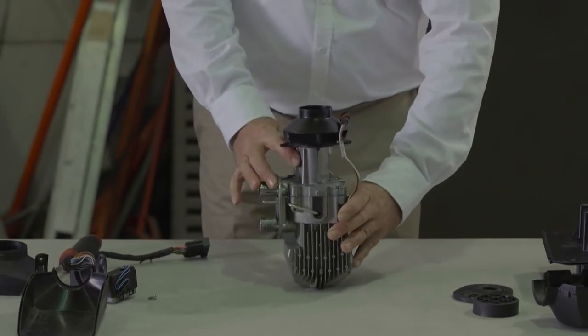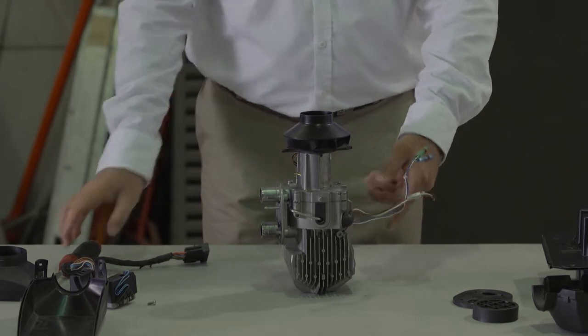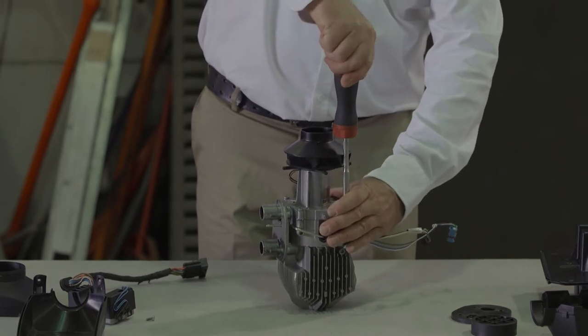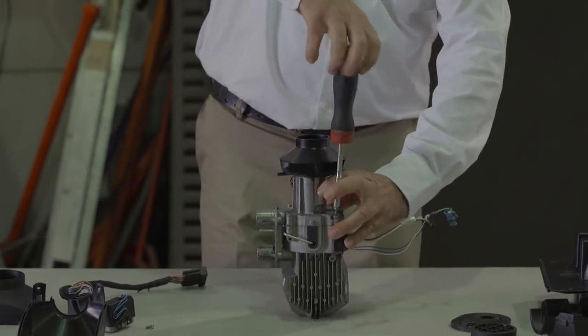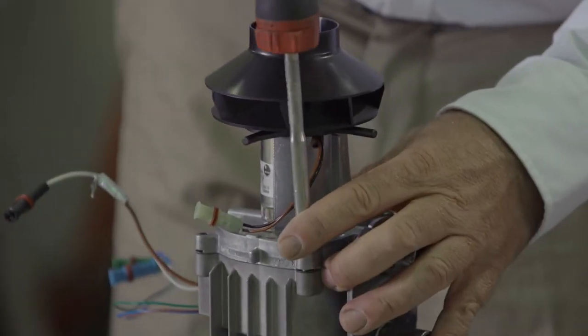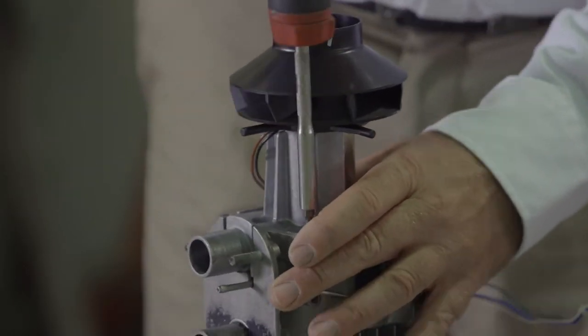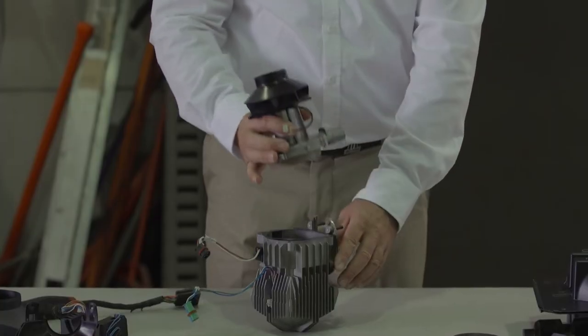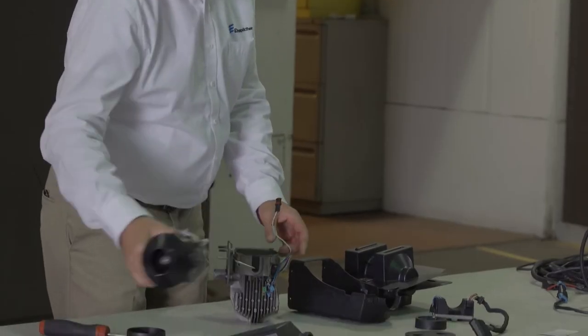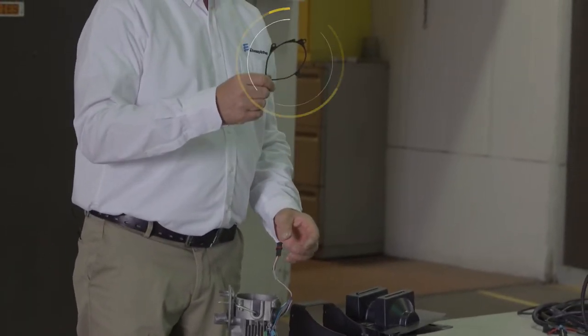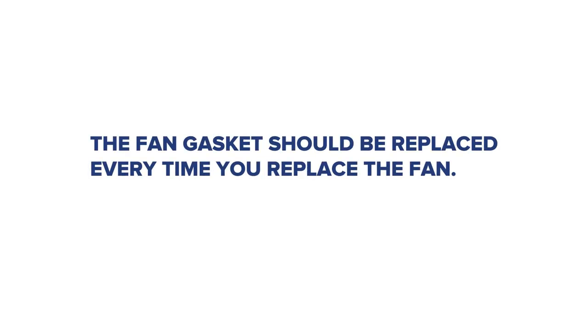At this point in time, there are four screws that are T20 Torx. You can remove the old fan. There is also a fan gasket. The fan gasket should be replaced every time you replace the fan.